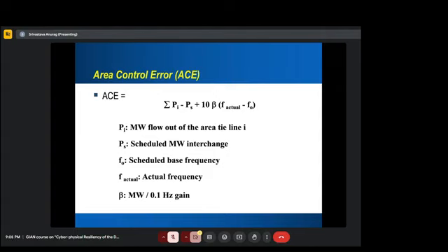Sigma Pi is the megawatt flow out of the area. We're talking about if UP is connected with MP, these two states, with 4 tie lines, and on each tie line Pi is flowing, P1, then P2, P3 and P4. If we sum it up, then we'll know how much power is flowing from one state to another state. And then we know that it should be less than 200 megawatt, but it is flowing like 300. So find the difference, which means that we have to minimize generation in one area or one state by that much difference, right? So that we will reach the targeted value.